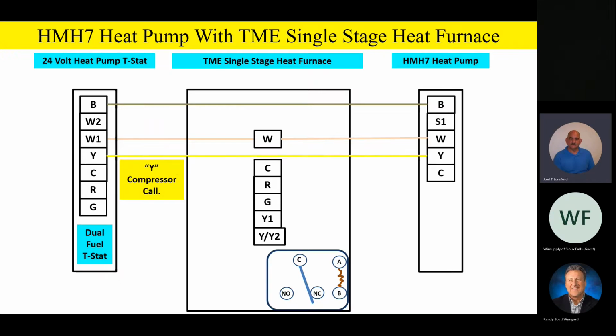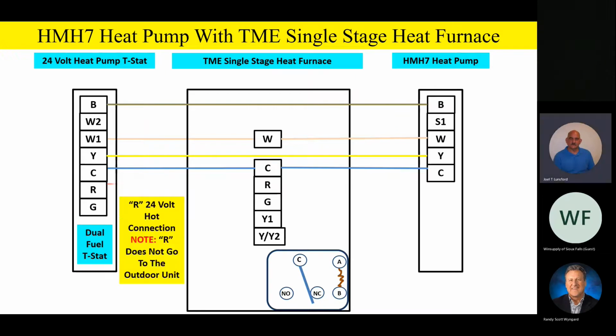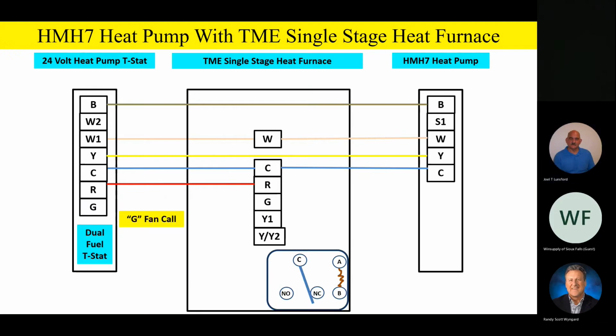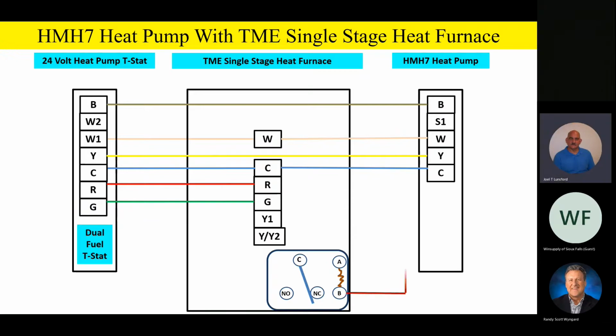Y terminal goes outside just like we did before. That's your compressor call. C terminal is going to be your 24-volt common, just like we had before. R terminal will be our 24-volt hot. Now remember, team, that does not go to the outdoor product. It just goes strictly between the thermostat and the indoor product. G terminal will be our fan call, just like we had before. G goes to G. Now please remember, we're looking at a furnace. We need a dual fuel thermostat if we're going to be hooking this up to a furnace, a heat pump with a dual fuel function. Other than that, it's pretty straightforward like we had before.